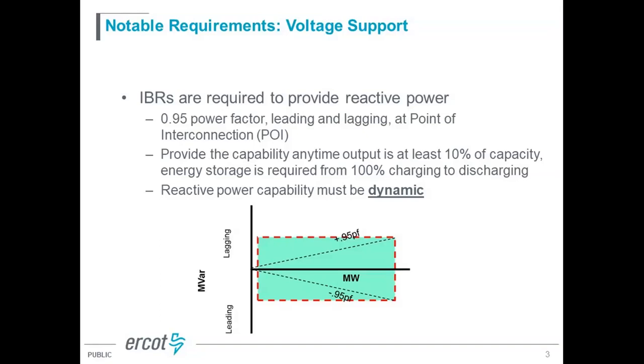In addition, those reactive supports must be dynamic. And recently we introduced voltage support requirements for energy storage, which will be required to provide voltage support across the full range, from 100% charging to 100% discharging.